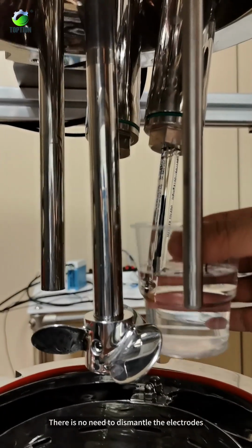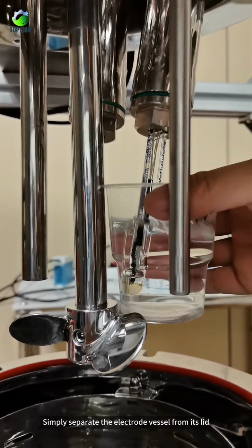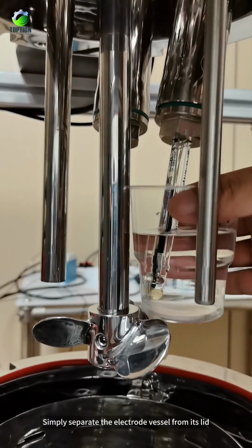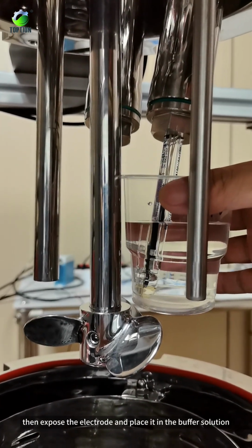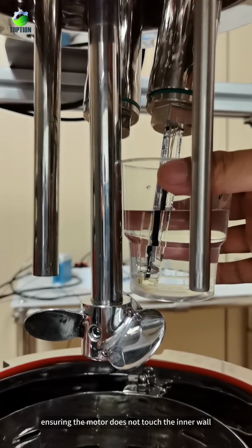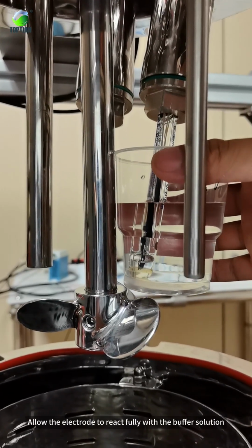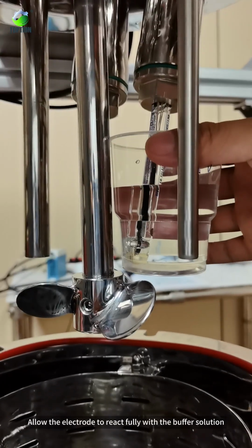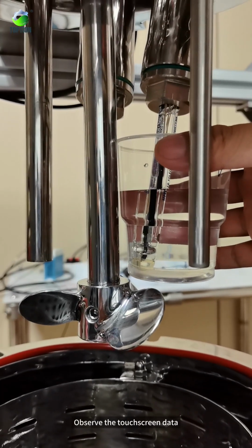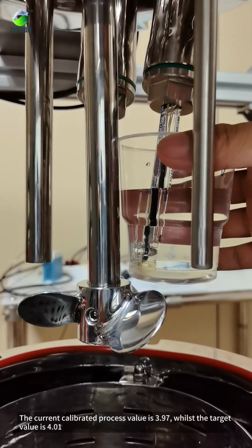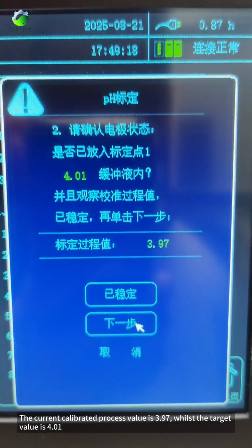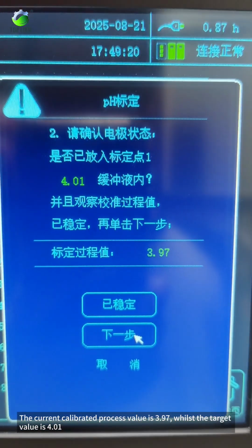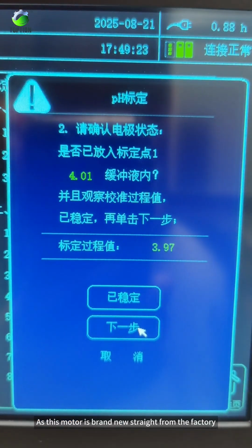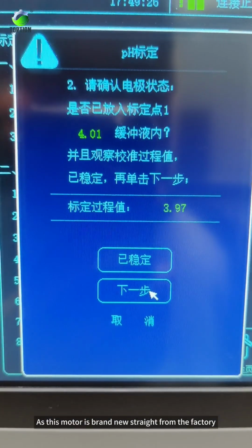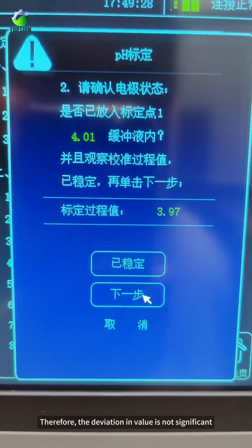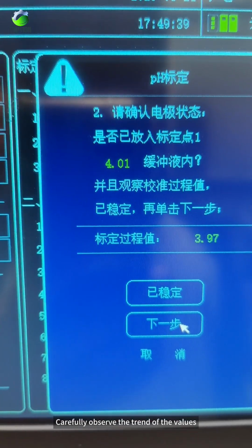There is no need to dismantle the electrodes. Simply separate the electrode vessel from its lid. Then expose the electrode and place it in the buffer solution, ensuring the electrode does not touch the inner wall. Allow the electrode to react fully with the buffer solution. Observe the touchscreen data. The current calibrated process value is 3.97, whilst the target value is 4.01. As this electrode is brand new straight from the factory, the deviation in value is not significant. Carefully observe the trend of the values.